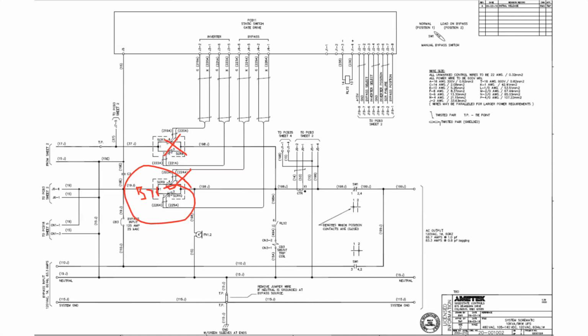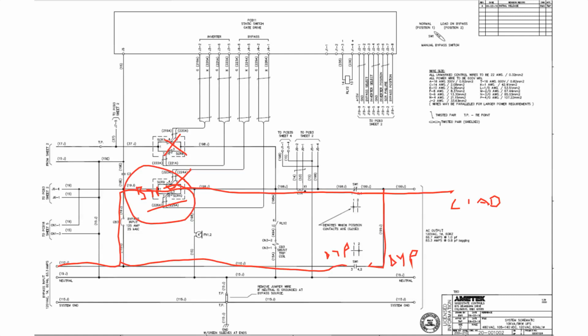But before that one went off, the bypass one would be turned on. So power would be flowing now up here through this static switch out to our load circuits. You say, well, why is that important? It's actually very important because now when you follow this one down here, we have bypass on this side of the switch, and you can see we have bypass on that side of the contact inside the manual bypass switch. And bypass are the exact same. They have to be, because they're the same supply. They are the exact same frequency, the exact same voltage, and the exact same phase relationship. It's impossible for them to not be the same unless the system's been connected incorrectly from the start.